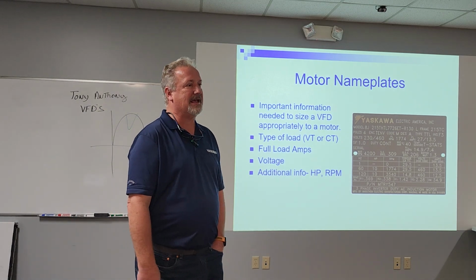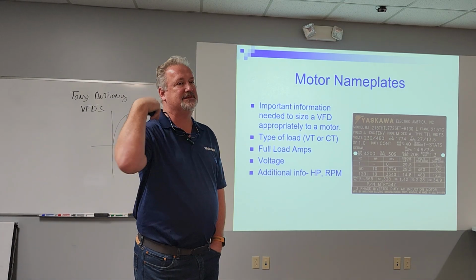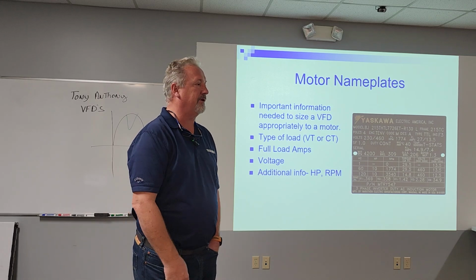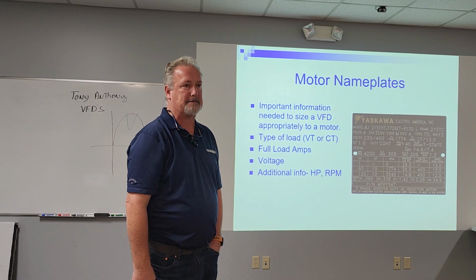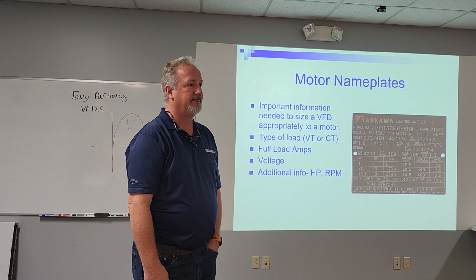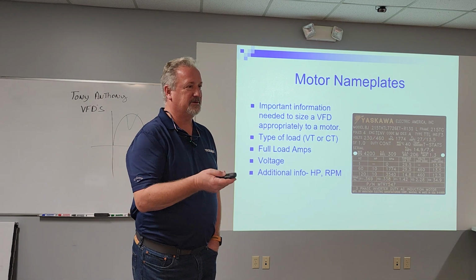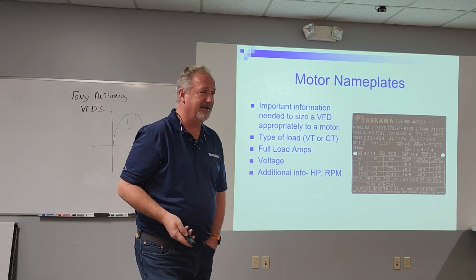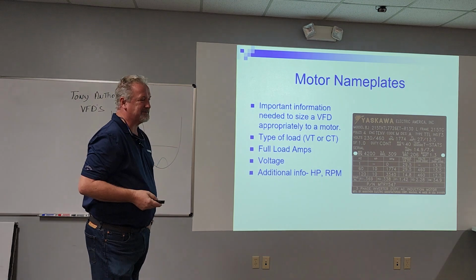If somebody calls you up and says, hey, I need to put a drive on this motor on this fan, what do you need to know? How much flow? Voltage, full load amps. Application. I could kiss you, because you didn't say horsepower. You said full load amps.